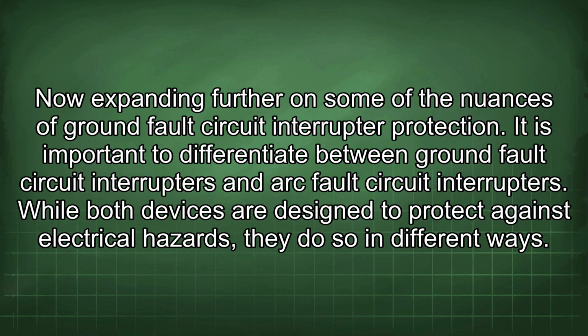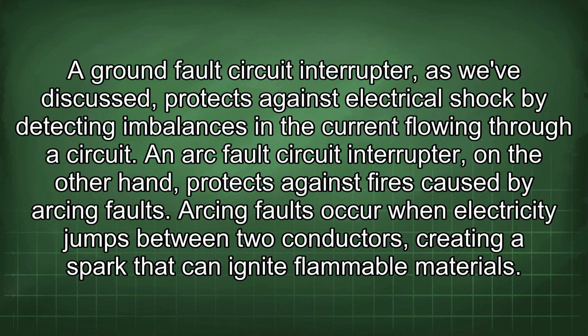Now expanding further on some of the nuances of ground fault circuit interrupter protection. It is important to differentiate between ground fault circuit interrupters and arc fault circuit interrupters. While both devices are designed to protect against electrical hazards, they do so in different ways. A ground fault circuit interrupter, as we've discussed, protects against electrical shock by detecting imbalances in the current flowing through a circuit. An arc fault circuit interrupter, on the other hand, protects against fires caused by arcing faults. Arcing faults occur when electricity jumps between two conductors, creating a spark that can ignite flammable materials.